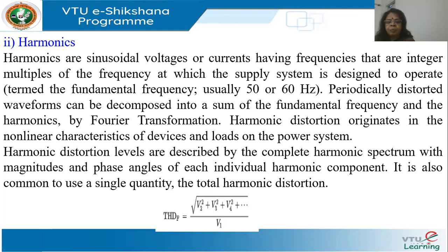Of interest. When is it of interest? When its magnitude is significant. If it's too low, it's not of interest. Divided by V1, where V1 is the RMS value of the fundamental. The same is the definition for THD of current also. It will be the square root of I2 squared plus I3 squared plus I4 squared, divided by I1.